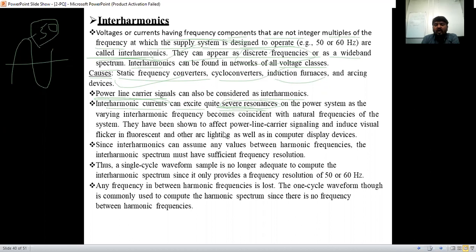They have been shown to affect the power line carrier signal. The power line carrier signals we are going to consider as interharmonics. So they have been shown to affect the power line carrier signaling and induce visual flicker. The flicker is going to be induced in fluorescent and other arc lighting as well as in computer displays. Some computers use such display systems. The flicker will occur because of this coincidence of the natural frequency and the interharmonic frequency. That produces the visual flicker that affects incandescent and fluorescent lighting as well as some computer devices.